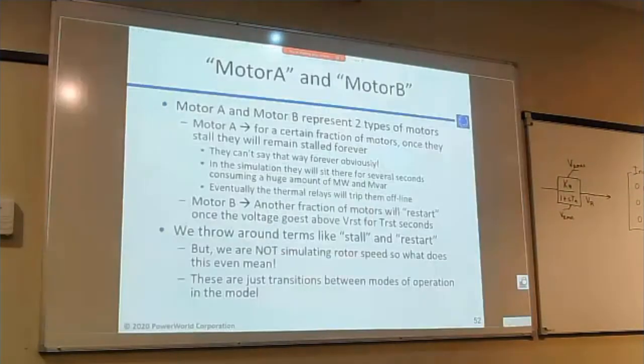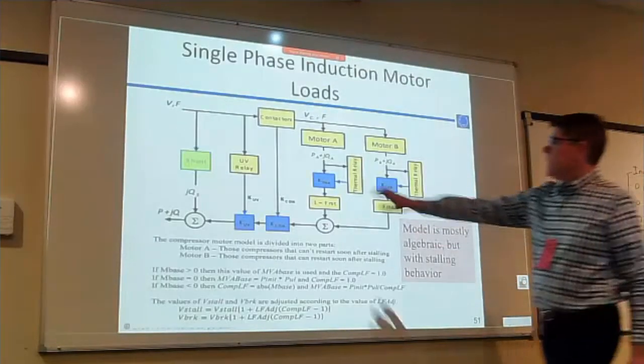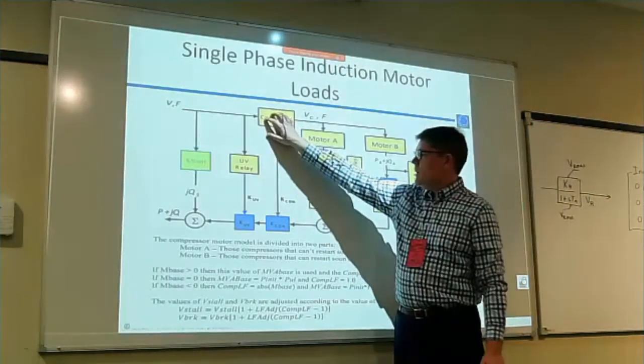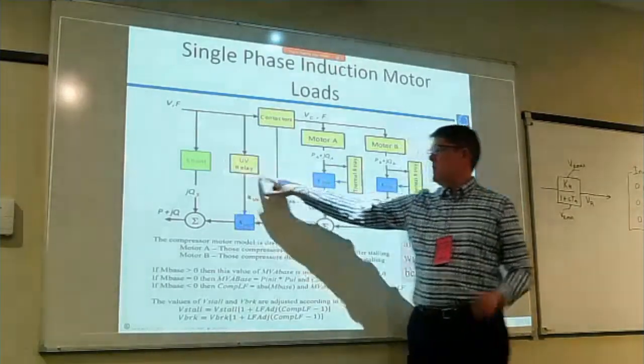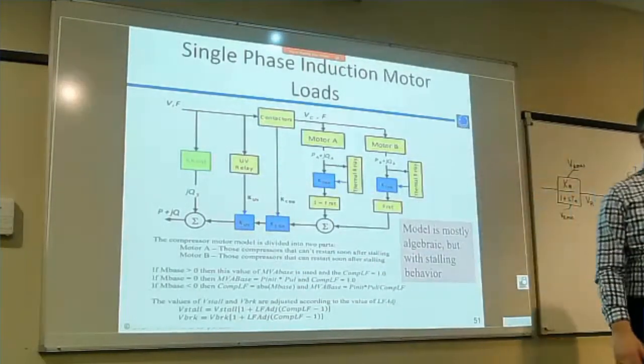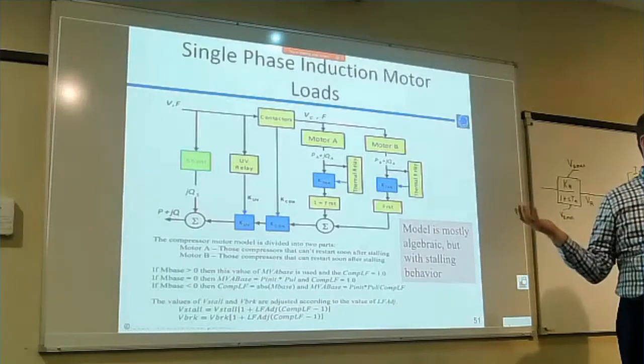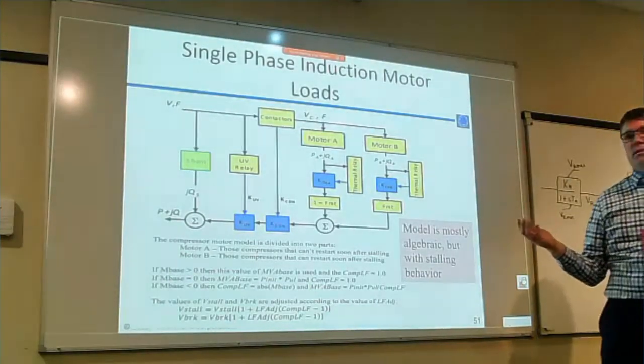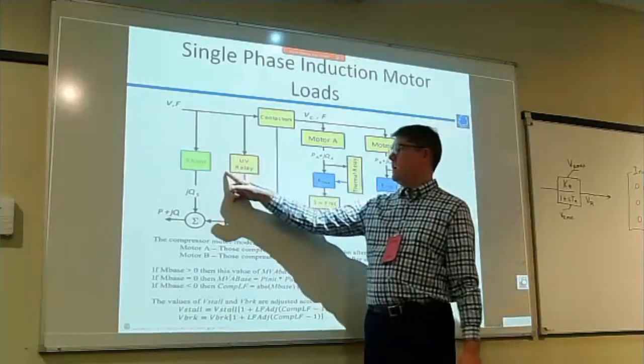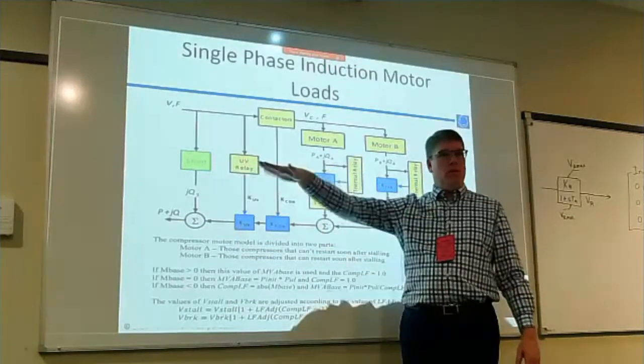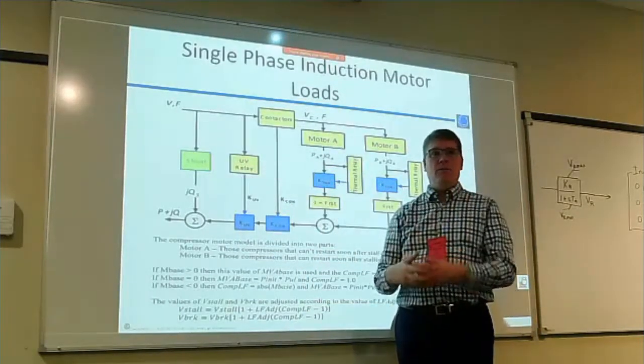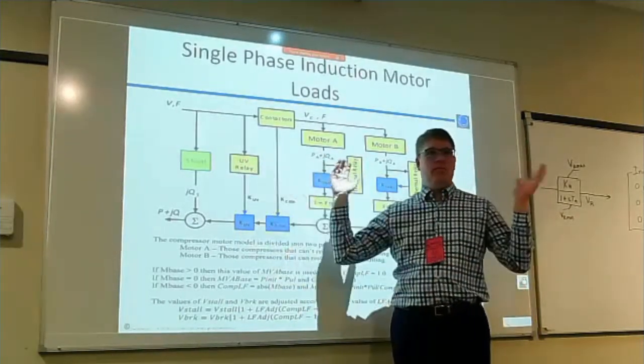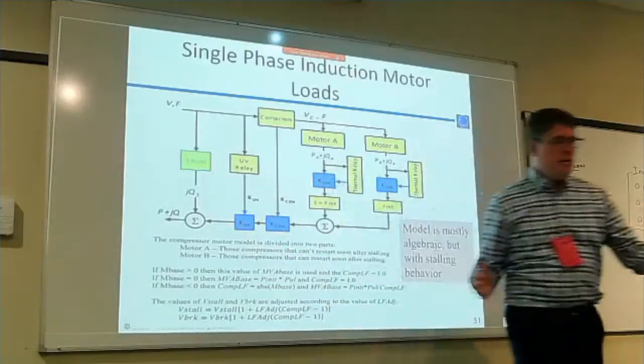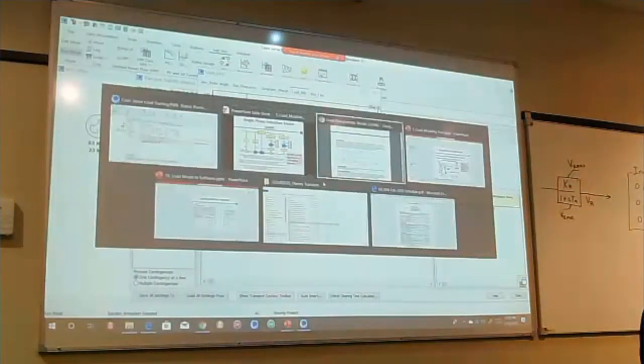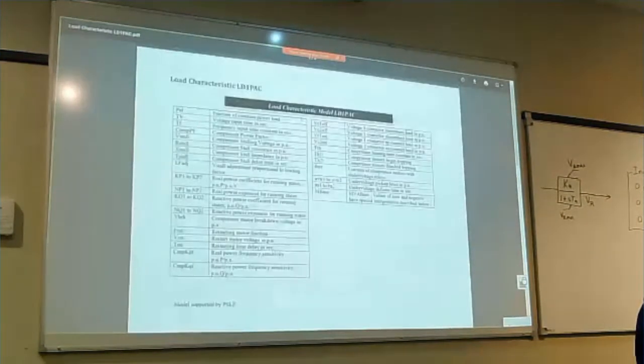So that is one method of tripping, and that's modeled right here. Another method of tripping is that there's probably some under voltage protection on some of these air conditioners. So there's a part of the model that says if the voltage falls below this level for this amount of time, then trip 30%.